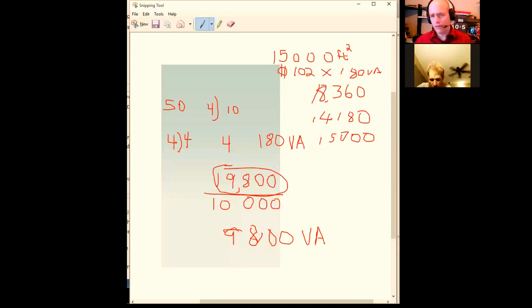Okay, so they give you the 18,360 as the first answer to pick from, and then they give you 14,180 as the second answer. The 18,360 is the answer if you just did it straight across the board without any derates. Yep. Similar to this one down here, the 14,180 would be as if you did take the calculated derate for the receptacle loads.